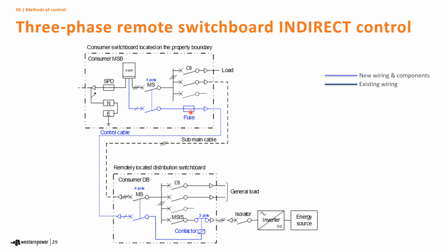The control cable doesn't need to have a lot of current carrying capability because the coil circuit will only draw a small amount of current, but you'll need to ensure it's suitable for the situation, suitable for not too much voltage loss to the contactor to make sure it works properly. Again, similar, you've got the 3-pole controlling the inverter downstream of the main switch inverter supply.